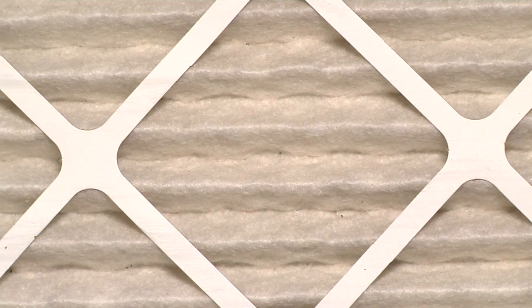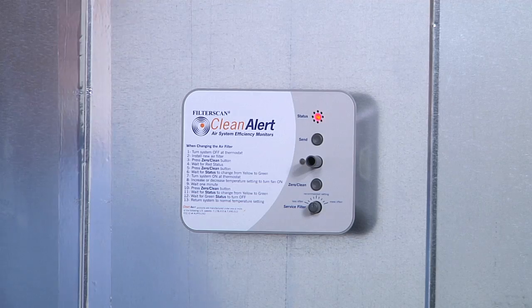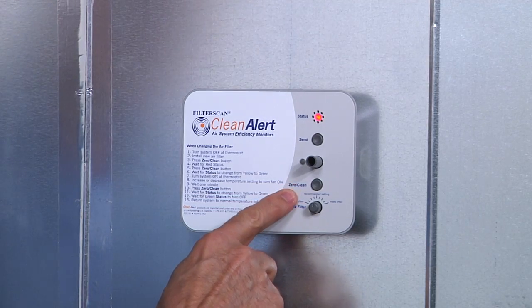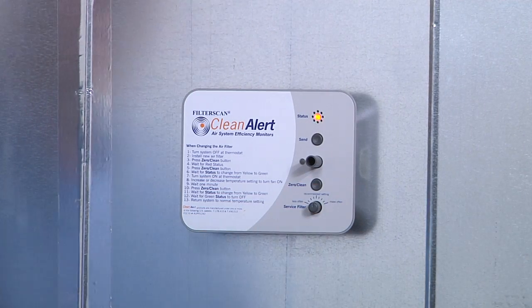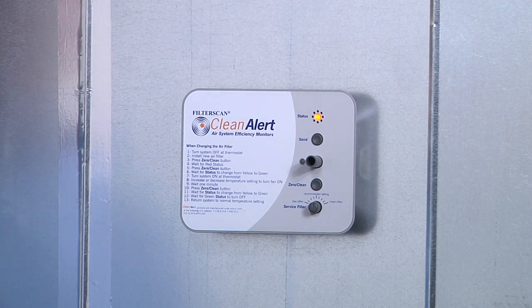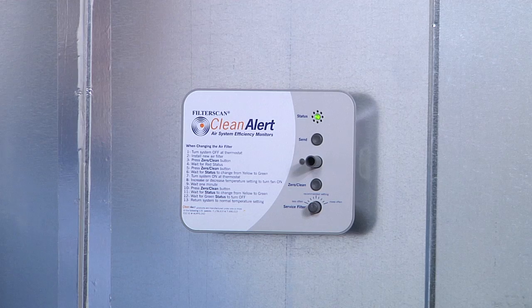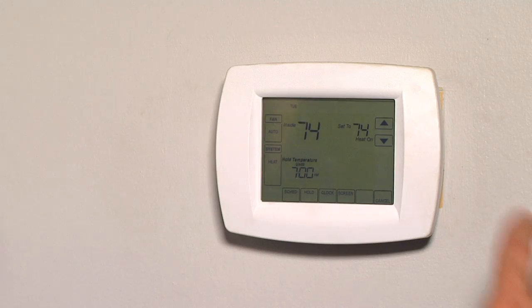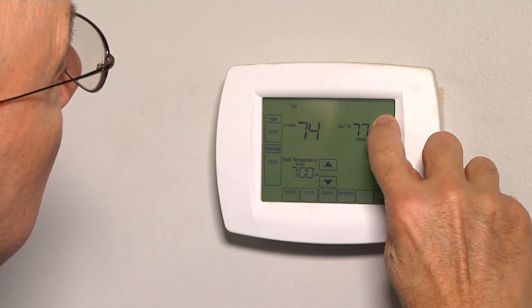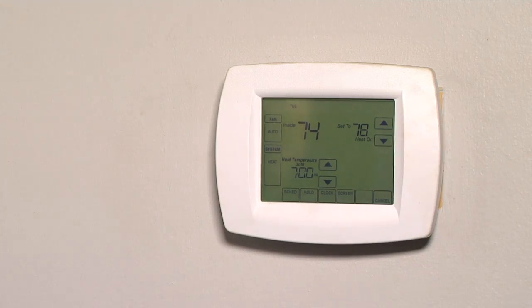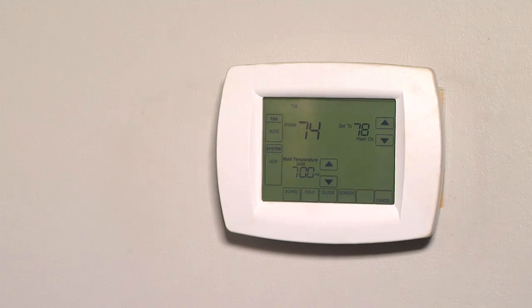Install a clean or new air filter into the HVAC system. Depress the Zero Clean button once. The status LED will blink yellow for several seconds while the Filterscan records the system's fan off condition, then turn to blinking green. This indicates proper operation and that you are ready to move to the next step. Adjust the thermostat temperature adjustment to either increase or decrease the room temperature by at least 4 degrees, enough to signal the HVAC system to turn heating or cooling on.